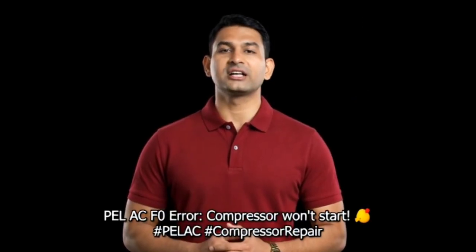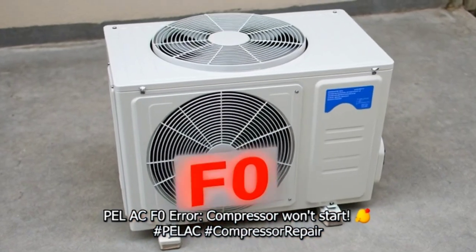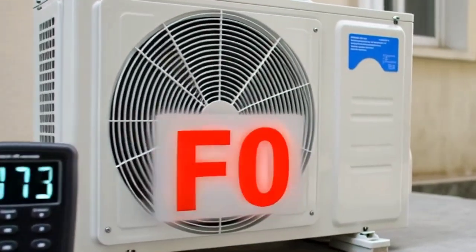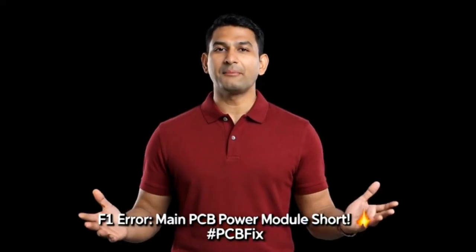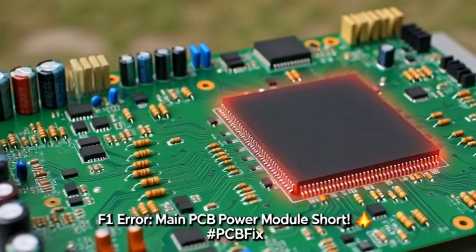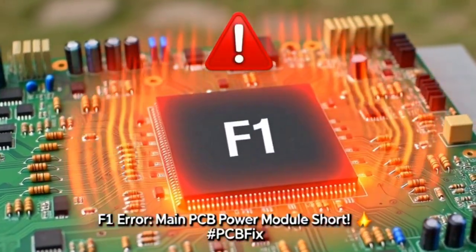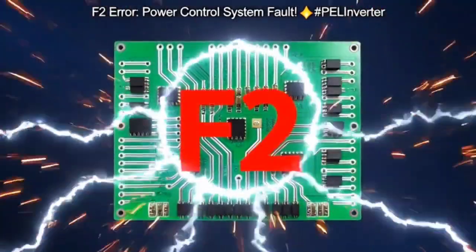F0 means the compressor can't start. Check your voltage or PCB. F1 indicates the IPM power module on the PCB is shorted or overheated. F2 is a PFC fault caused by unstable power or voltage issues.